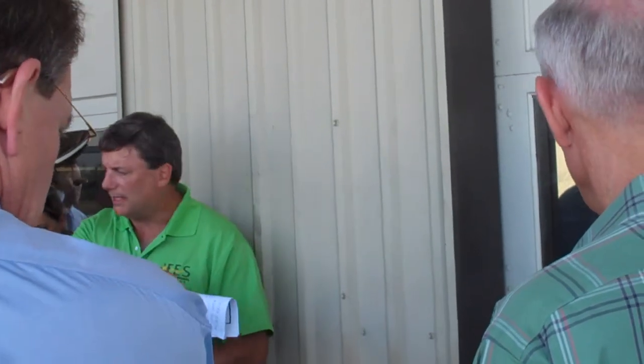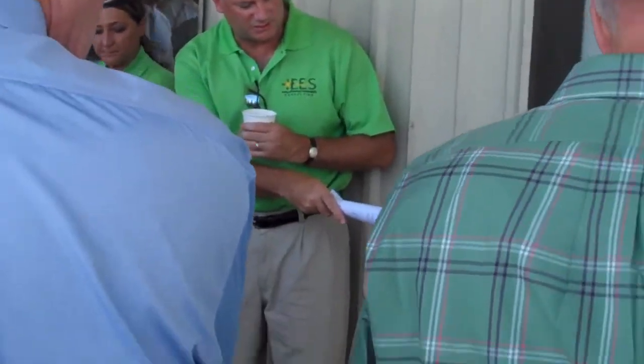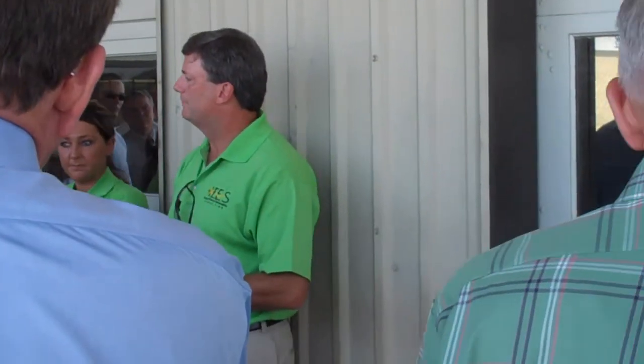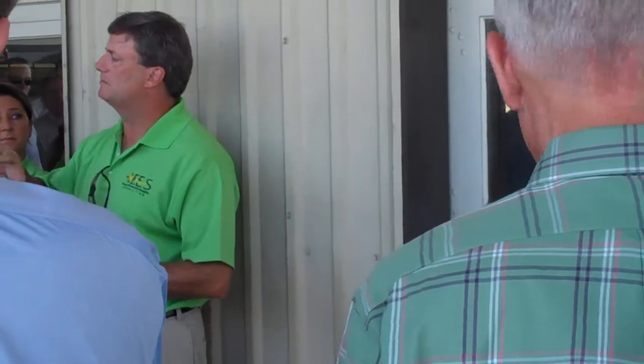The lighting in this building, and Rusty will demonstrate in a minute, had some old 400-watt metal halide fixtures like this one on the ground. They were inconsistent, many were burned out, and the lighting had degraded—so there's both a quality of light issue, possibly a safety issue, and just an energy inefficiency issue.